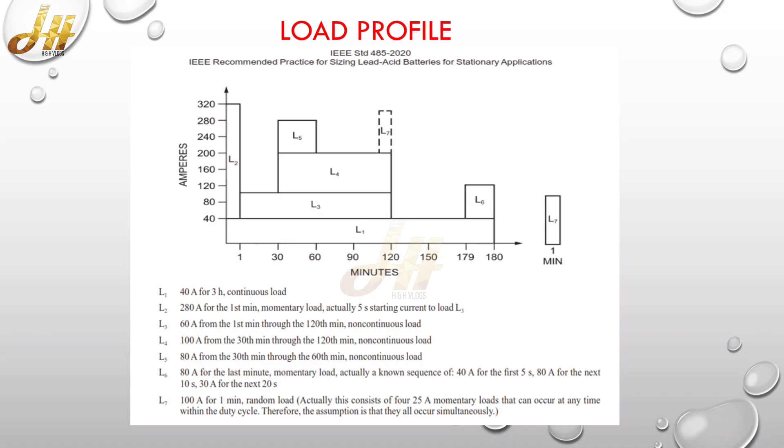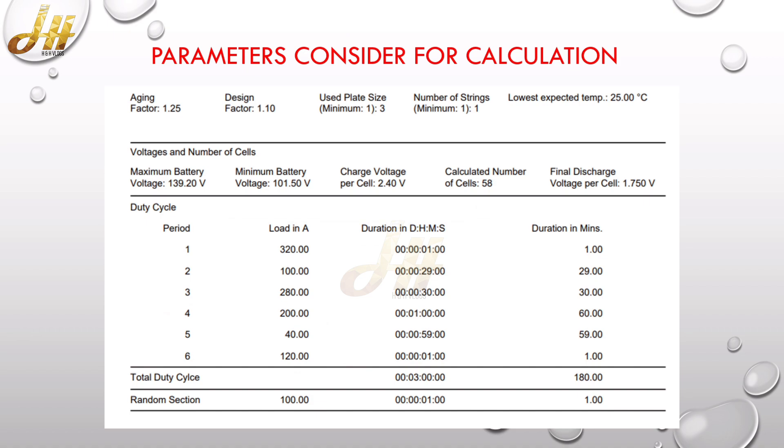And added to the calculated sizing capacity. For sizing the battery, we feed the details in numerical form in the software, and there are other factors or parameters considering the calculation, which are aging factor 1.25, design factor 1.10, and the lowest expected temperature which is 25 degrees C, and the final discharge voltage per cell is 1.75 volt. So the total minimum voltage of the battery set is 101.50.